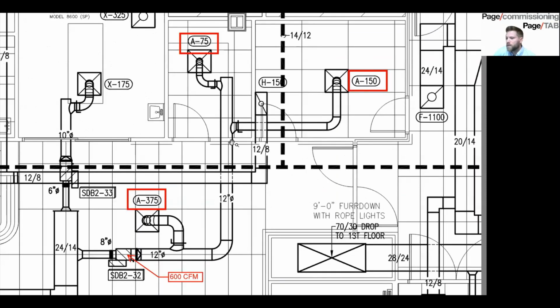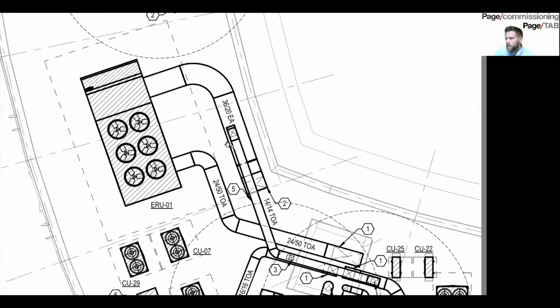So we're good there. So as you can see, based on what we found, we had two sized correctly, one sized incorrectly. And this, make no mistake, is a big deal. 2000 CFM undersized or 2500 CFM undersized. It would be tough for that unit to speed up and get that. That may be a fan change because it might overamp once it finally gets the CFM. So you may have to change out the fan, the motor, which may even require wiring changes, or you may change out the ductwork. Huge cost if this is already installed. So do it as early as you can. And this will save you time, because something like this more than likely will delay the project months, if not maybe even a year. I've seen in the past.